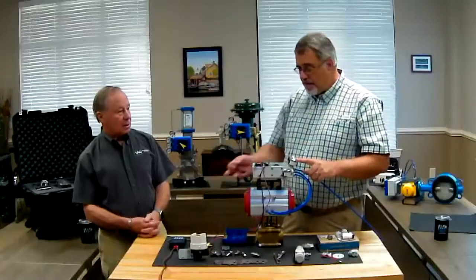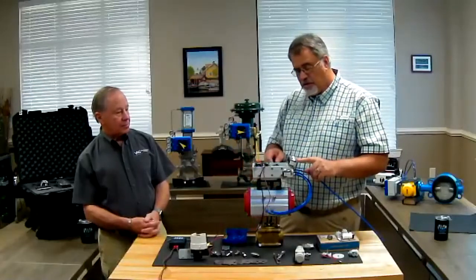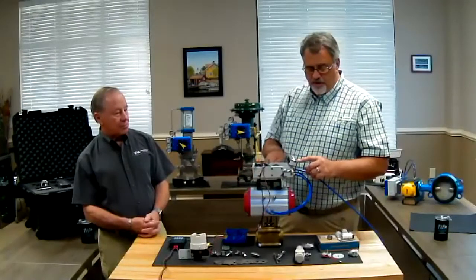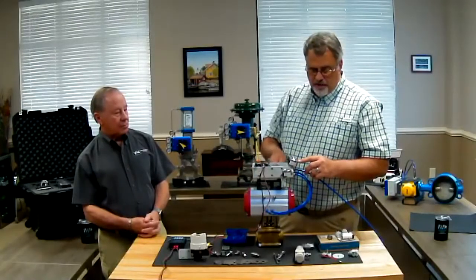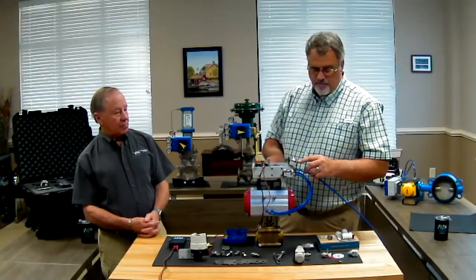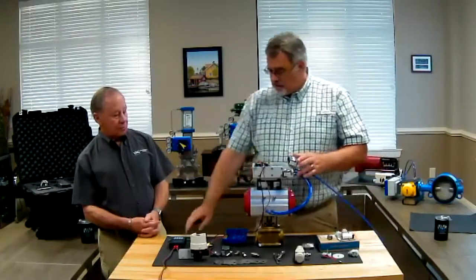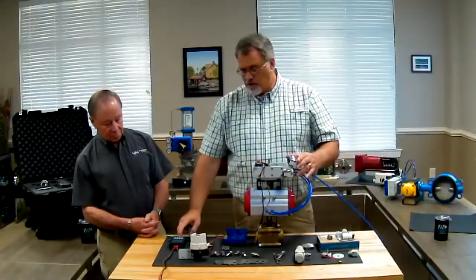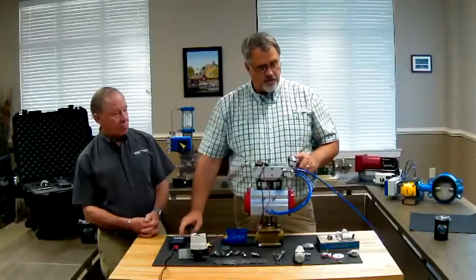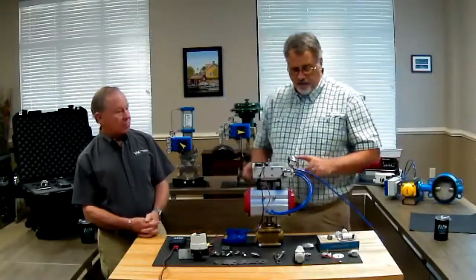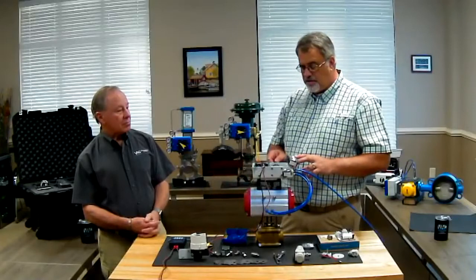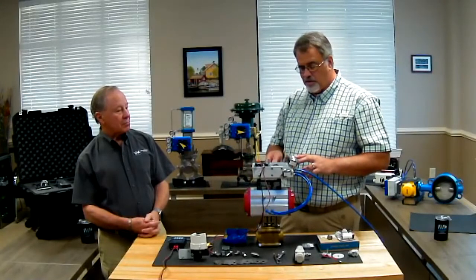Now I'm going to do span. I put 20 milliamps on the positioner, and same thing. I'm going to bring the needle up off the pin, and then back it down until it just touches. So that's my span calibration. If I go back to 4 milliamps and this gauge reaches 0 PSI, I've calibrated this positioner. In this case, I did it a little too sensitive, and I need to make a small adjustment.